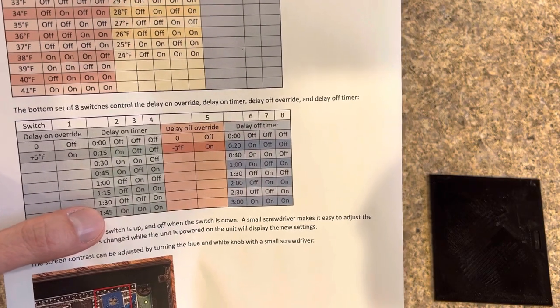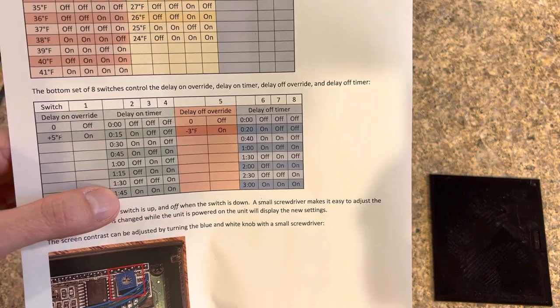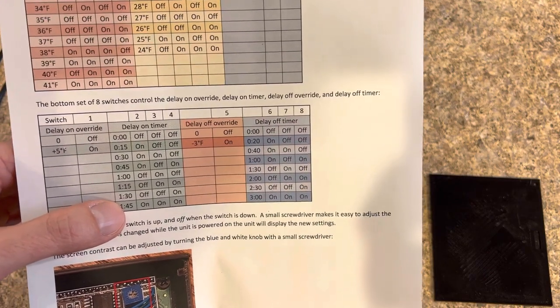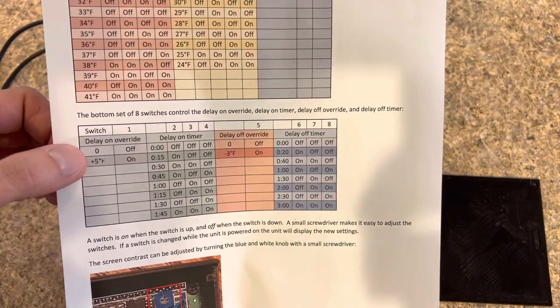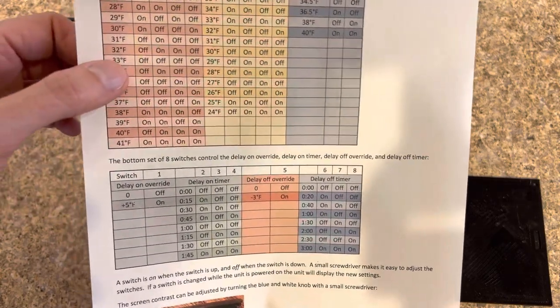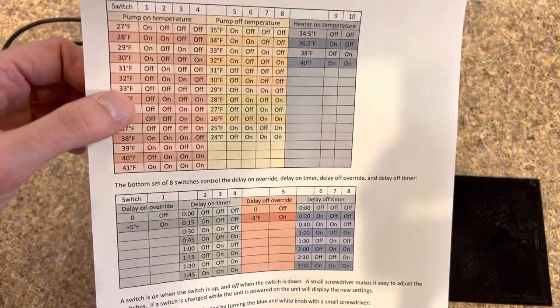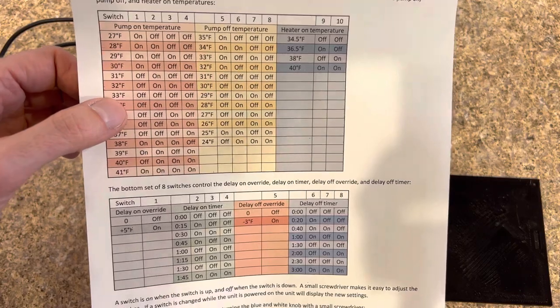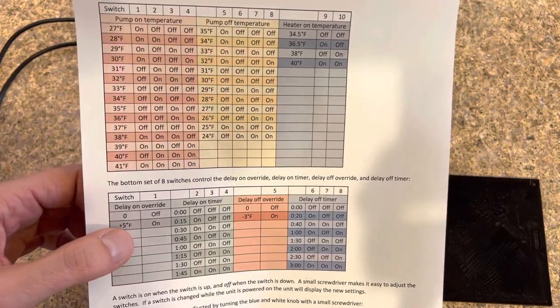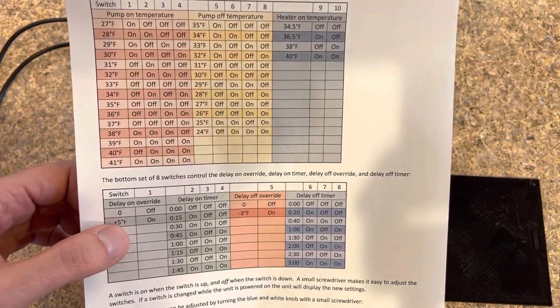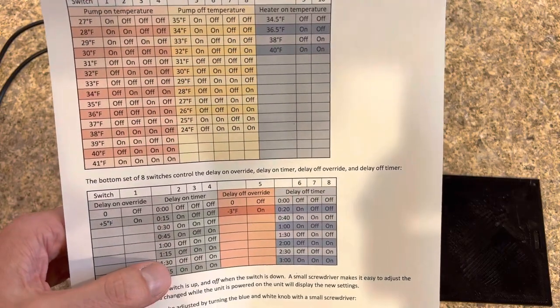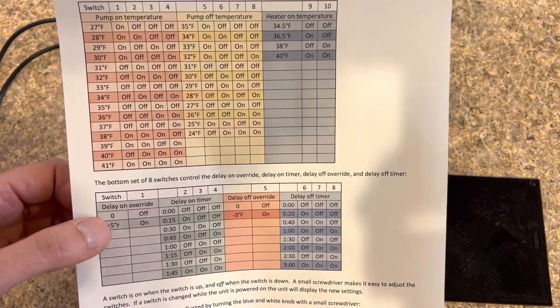But if the temperature continues to go up, say 34, 35, 36, 37, very quickly, you can do a delay on override. So if you have it set, for example, to the default of the pump turns on at 33 degrees and it turns to 38 degrees, which is a +5 degree difference, the pump will ignore any delay on timer you have and automatically turn on.